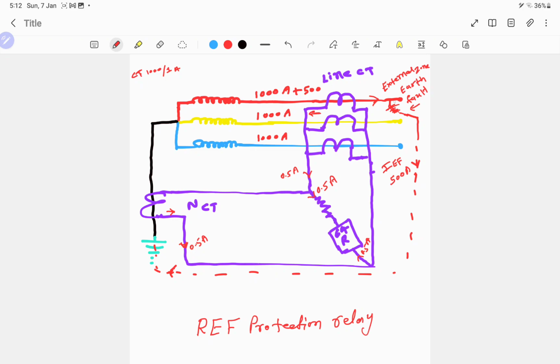Now in normal condition, when the load current is flowing from the winding towards the outside point, it's flowing like this. When the current is balanced, the total vector sum of the neutral current, IA plus IB plus IC, the vector sum of the balanced three-phase current will be 0. So when the load is balanced, the overall current of all three CTs will be 0 amps. So there will be no current flowing through the CT, and no current flowing through the neutral, because it's the balanced current. So there will be no current detected by the neutral CT or the line CT, and the relay will not operate.